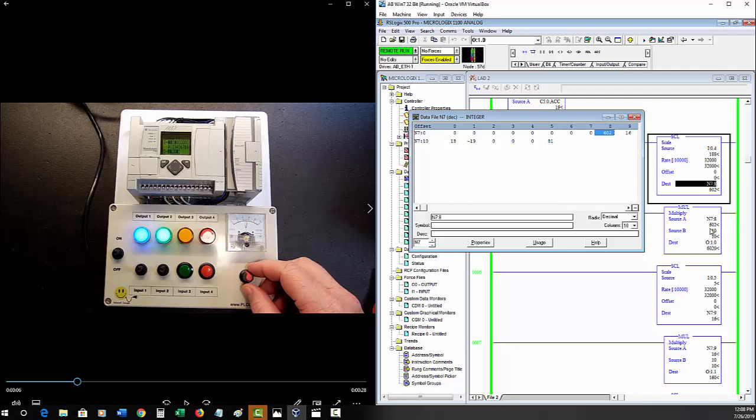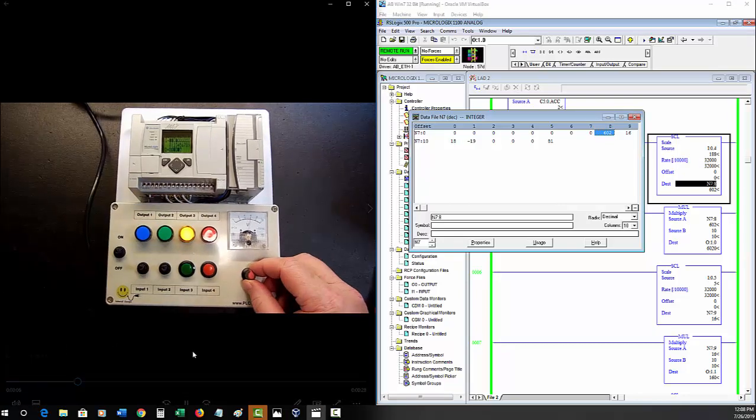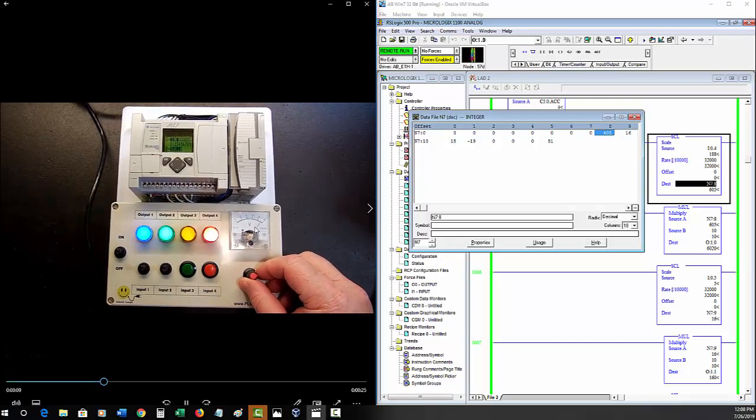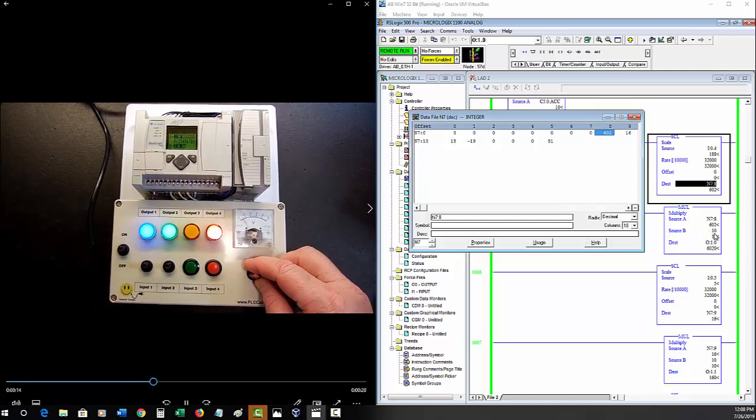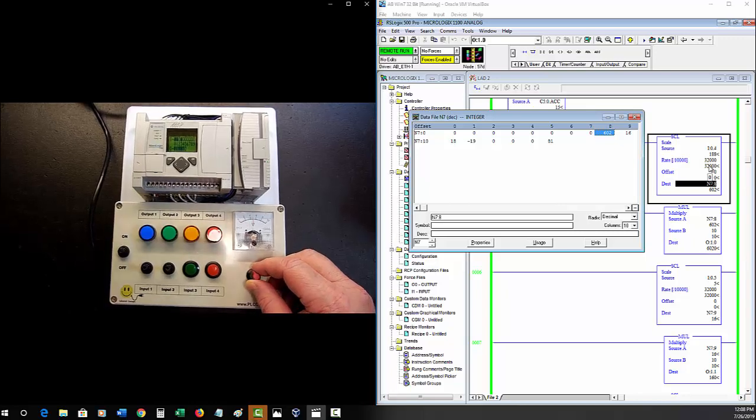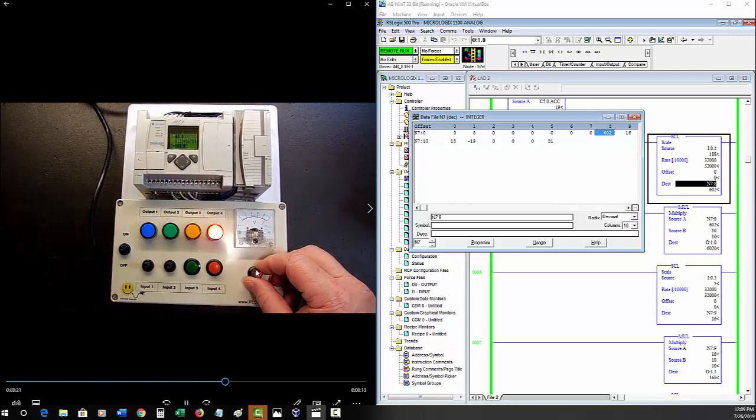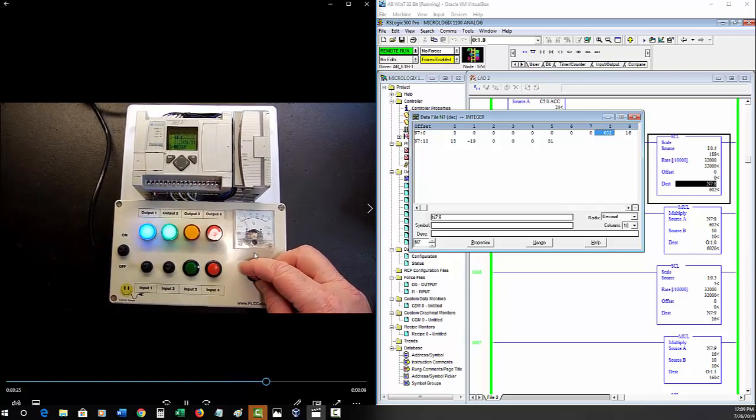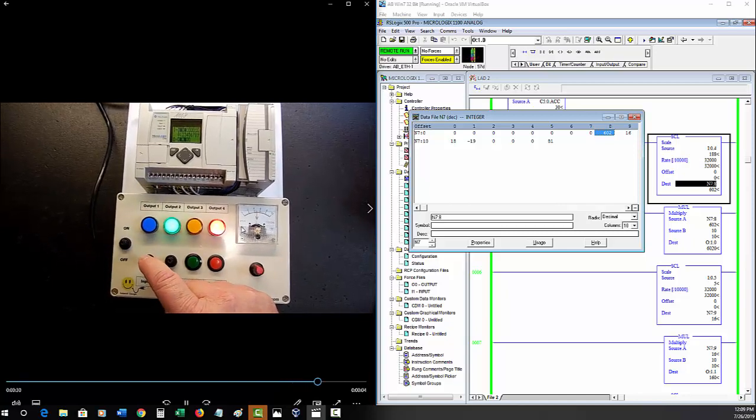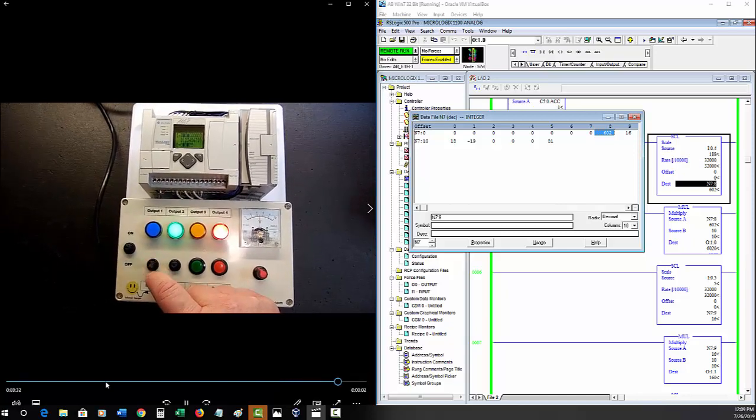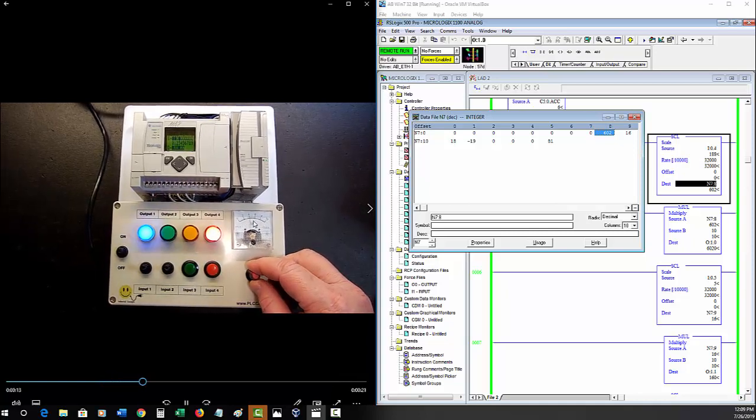Now we're going to multiply it. So we take N78, which is a value of 602, multiply it by 10. And we move our destination is our output word. So our output word is O:1.0, which is going to be our output card here. And it's going to be one on here, which is going to be our meter is what we have it wired to. So as we turn the pot, we're going to see that. And that's why it's a straight 10 multiplication. And the scaling is the way that it is. Because what we're doing is when the pot's all the way at 10, the meter reads 10. When the pot's at 50, the meter reads 50 or 50%. And when it's at zero, then the pot should go back down to zero. So you should be able to see that scale back and forth there.